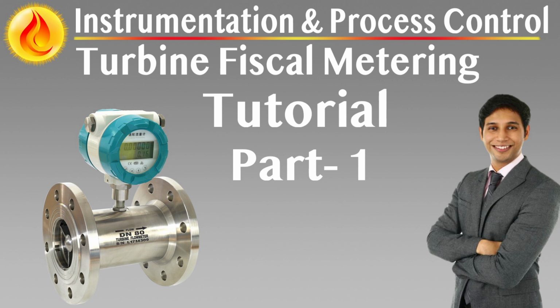The validation footprint of a meter includes not only calibration factors, but full metrology and geometry checks. Every calibration certificate must disclose systematic error trends, range-specific deviations, and measurement uncertainty to allow precise system-wide uncertainty reconciliation.